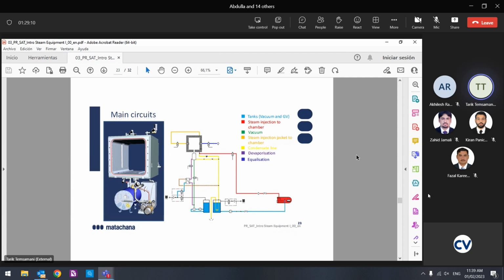In the case of heating with our steam injection, we get steam from the jacket, from the higher side. Once we put steam inside the jacket, there is condensate here, and this line is the continuous purge. Always we are removing the water from the jacket, and in the heater we have only steam. So once we get the steam from the jacket to the chamber, we get only steam without humidity, without water. So from that we get steam to the chamber in the orange circuit. Okay, it's clear? If not, I'm sorry.